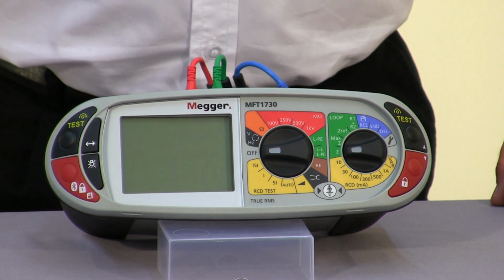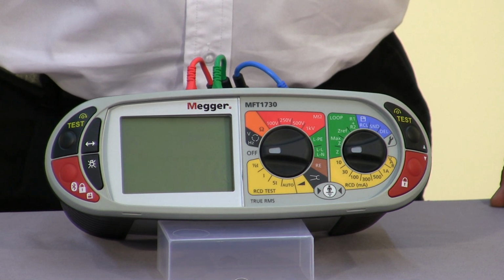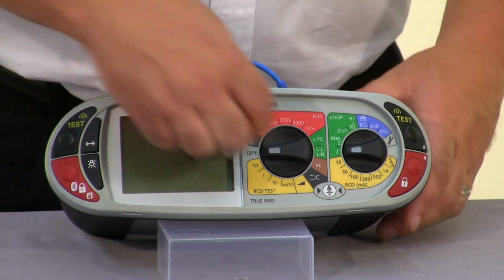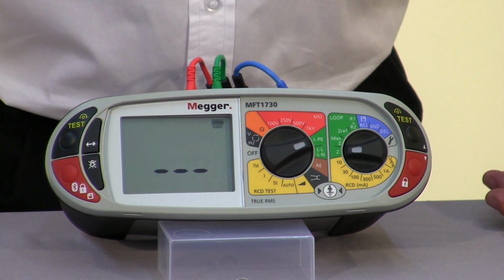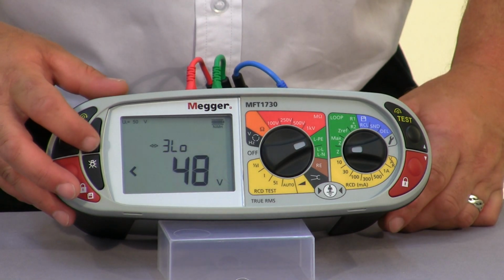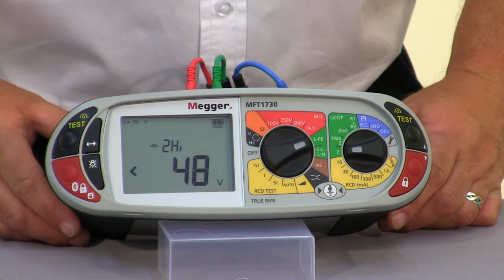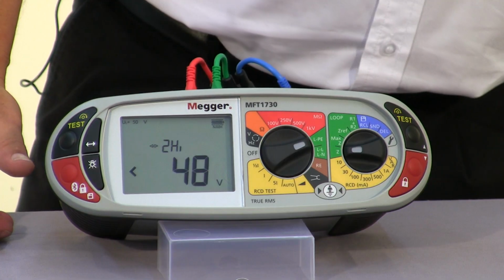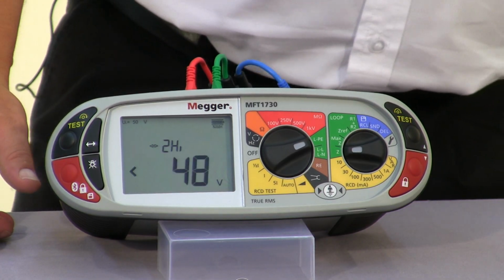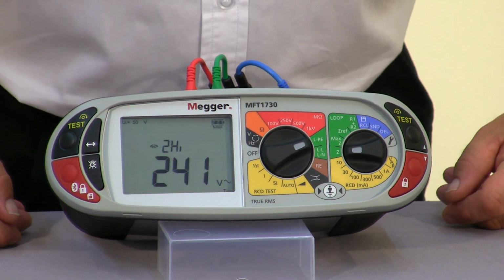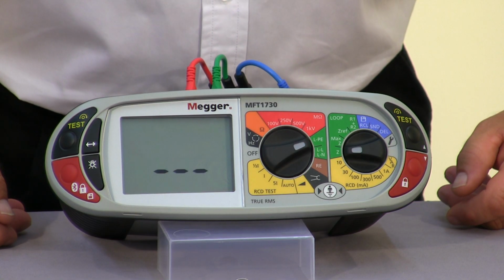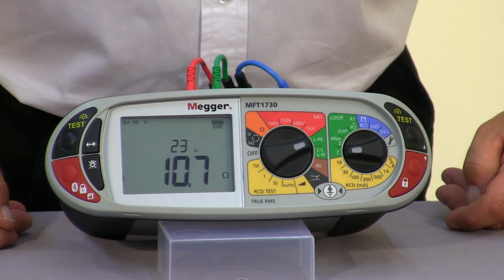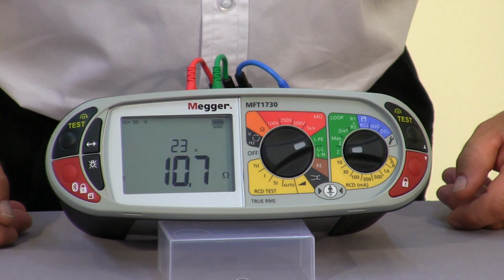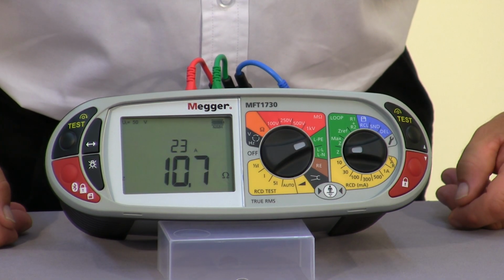The final earth loop test we'll look at will be the straightforward two-wire high current test. So selecting our LPE and our Z measurement, using the function key we can select our two-wire high current test, plugging the unit in. Again, auto start, and the reading 10.7 ohms and 23 amps PFC.